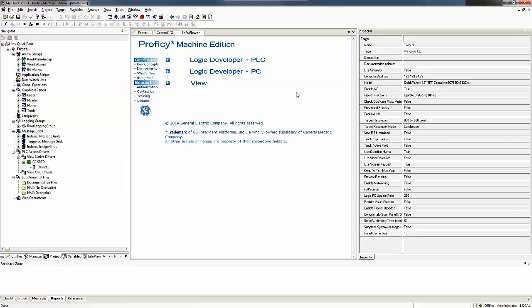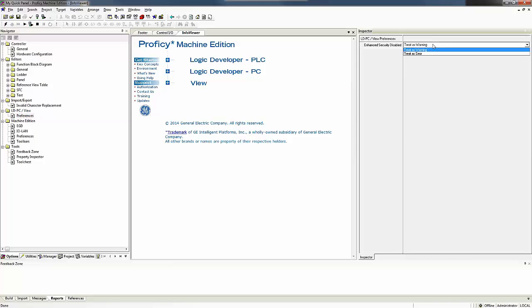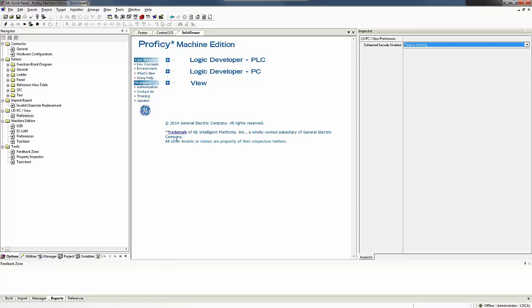Now Proficy Machine Edition by default has enhanced security enabled which requires a password to be entered into the QuickPanel. If you do not want to enter a password in, the enhanced security can be disabled by clicking on the options tab and then the preferences under LDPC slash view. And on the right hand side in my inspector, you need to change this from treat as error to treat as warning. That's the first step in not having to put a password in your QuickPanel.